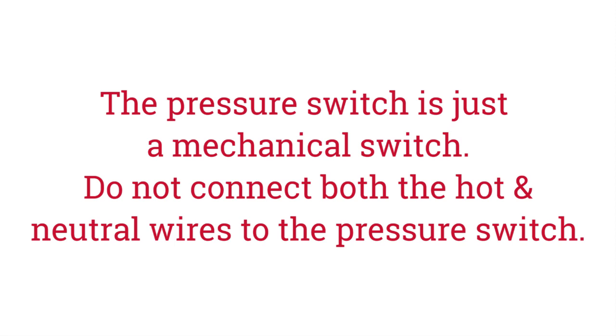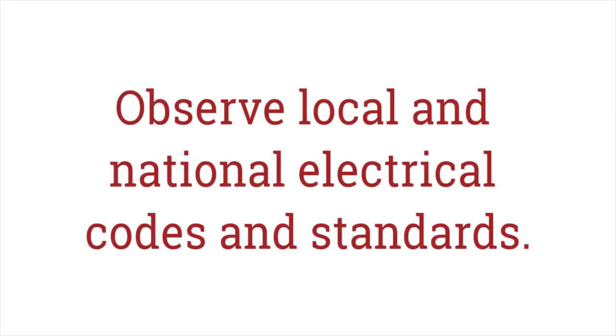The pressure switch is just a mechanical switch. It does not require power to operate, so do not connect both the hot and neutral wires to the pressure switch. First, observe all applicable sections of adopted local and national electrical codes and standards, and use an appropriate gauge wire for the load and length of wire run.